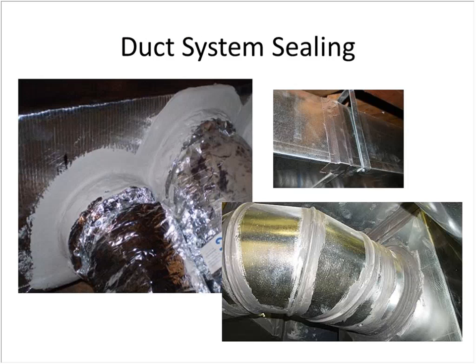Mastic is a little bit more of a manual process, but it's done with a paintbrush, and it'll stick where the tape may have a tendency to fail when it's in an environment where there's excessive heat and cooling changes or even condensation. And then the two on the right, the right top picture is a duct tape. It doesn't appear to me to be an approved duct tape or mastic, but the bottom one is a better example of every joint being sealed with a mastic.